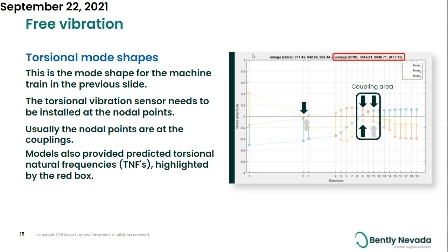The horizontal axis is the location along the rotor system, and the vertical axis is the normalized angle of twist. A lumped parameter model was used to create this plot, so those dots represent station numbers along the rotor. The lines show the shape of angular deflection across the rotor system. Generally, the steeper the line, the more stress there is at that location. Since the magnetostrictive sensor responds to stress, it is these locations with steeper lines that are ideal for sensor mounting.